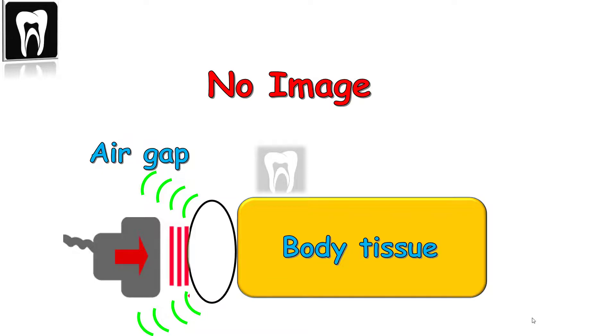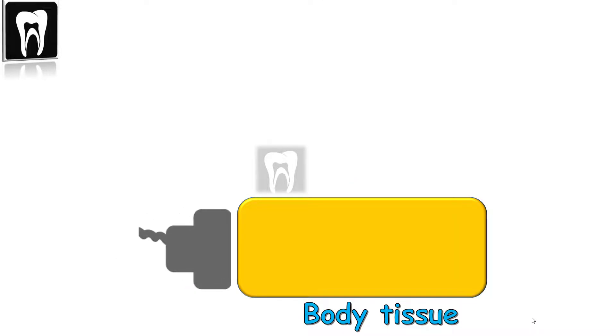Therefore, it's absolutely vital to make sure that there is no air bubbles between the probe and the skin of the patient.